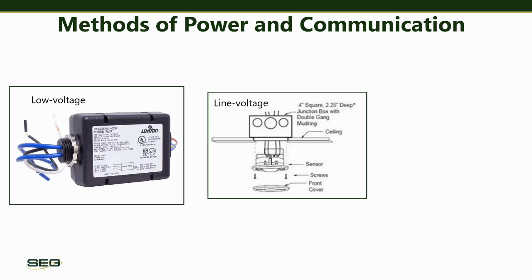Next up is line voltage. Line voltage sensors don't use a power pack, and they're suitable for applications where power pack installation is limited by a lack of space or access to junction boxes. Many only have the ability to switch a part of the load due to limits on how much power the sensor can safely handle, and they're often used for individual luminaire control in applications such as warehouses or for small loads.